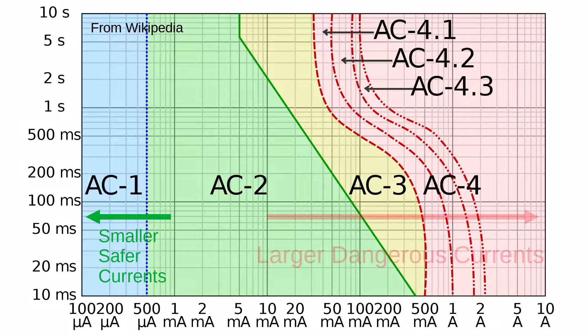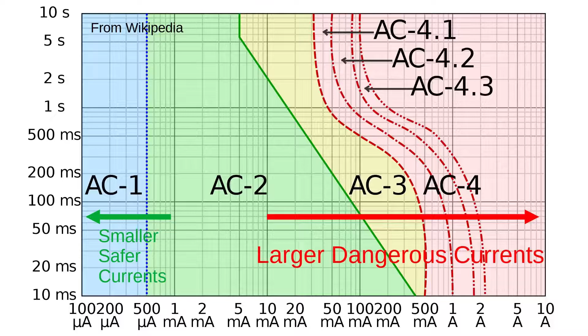As a typical rule, things less than 1 milliamp are probably okay, and things more than 10 milliamps are starting to get seriously dangerous. And these GFCIs are, in most countries, set up to trigger somewhere between 1 and 10 milliamps. And the isolation transformer, if it's properly built, will actually prevent there being virtually any milliamps going from one end to the other. It should only be in the very low microamps.